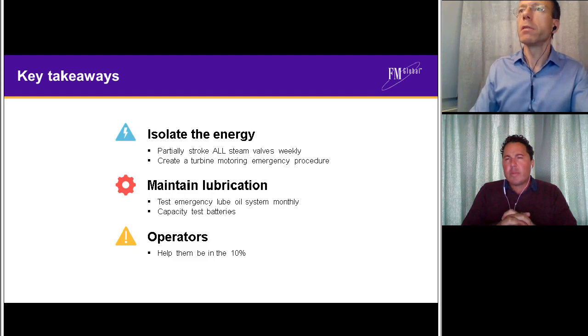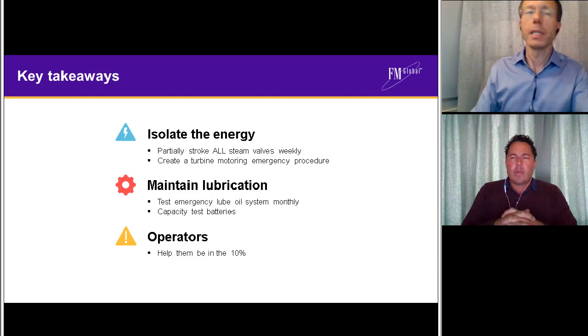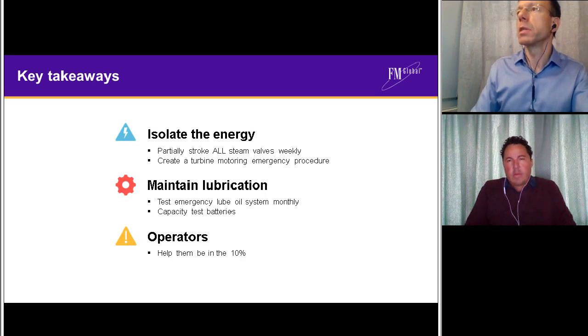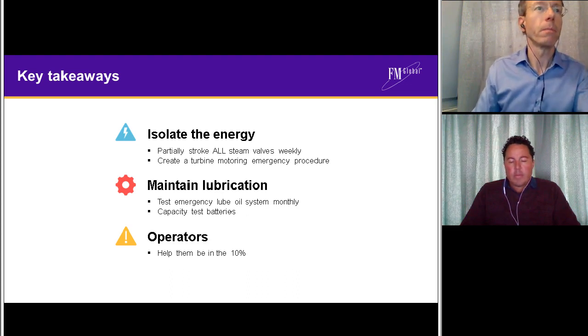Don, you stated that lead acid batteries, DC emergency supplies, should be replaced every 3 to 4 years. Is this realistic? Most lead acid battery systems in the UK power plants are in service for 10 to 20 years without an issue. Drop tests and regular maintenance are the norm. Please can you clarify where the replacement frequency has been derived from?